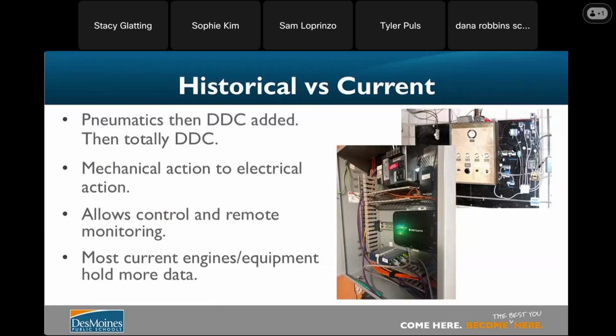Building automation systems have come a long way. They used to be controlled with air, pneumatics, and then digital or direct digital controls, DDC, came along. Now dampers and valves are moved with electrical action versus the mechanical action that it used to be. And it allows for a lot better, finer control on the equipment, and allows us to monitor things remotely.